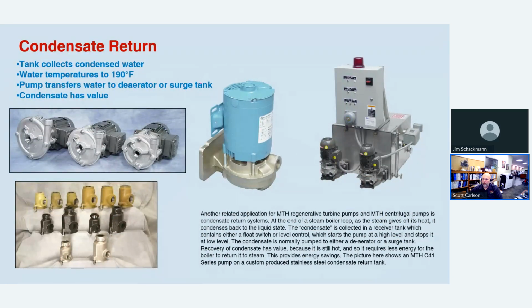Next, accompanying the boiler feed would be the condensate return. After the water has been traveling around in the piping, heating up whatever process it's being used for in heating, the steam condenses back into water and empties into a condensate return tank. With the condensate return tank, you can either put the water back into the boiler feed system, or you can go directly into the boiler with it. If you go into the boiler feed system, usually a centrifugal pump is acceptable. We do make a small line of centrifugals, a 4, 5, and 6 inch version.